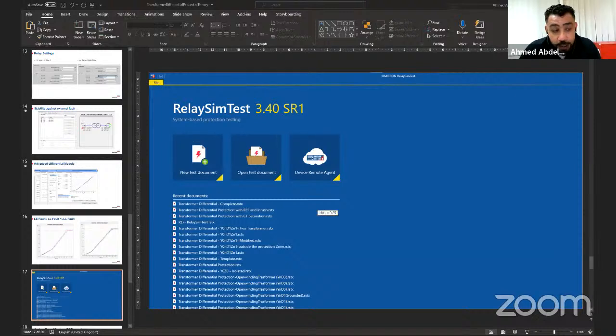From here, you can see the lowest dotted line, it's IDIFF greater, which is the minimum operating current. And here I have IDIFF greater greater, which is the unrestrained, and the relay characteristic. What is the last line, which is this line? It's a line of 45 degrees, because electrically, we don't have any possible way to have a fault in this region. Why? Because if you have a fault in this region, it means there is a third current source which you didn't put into your system.